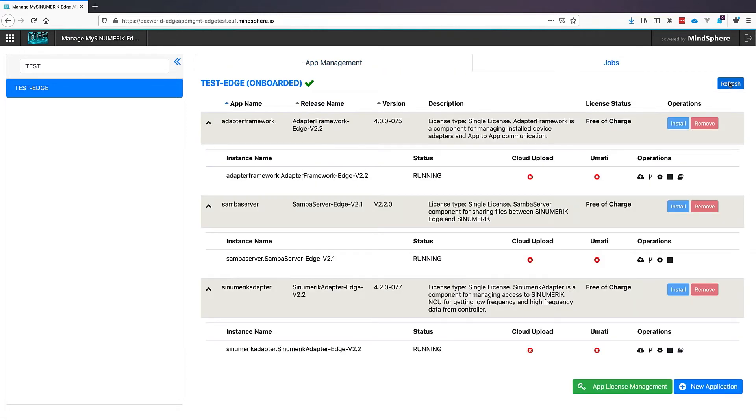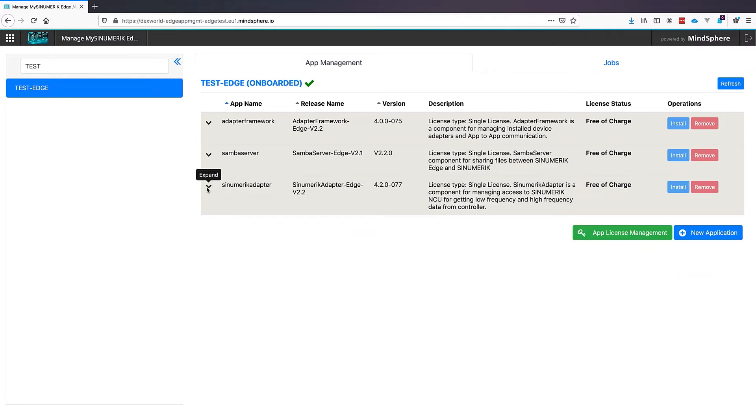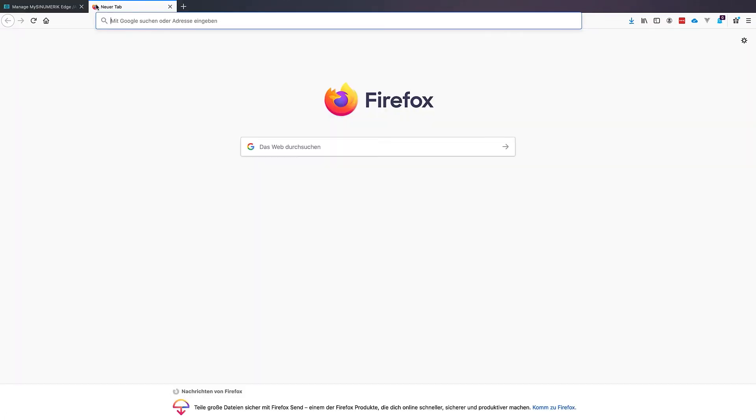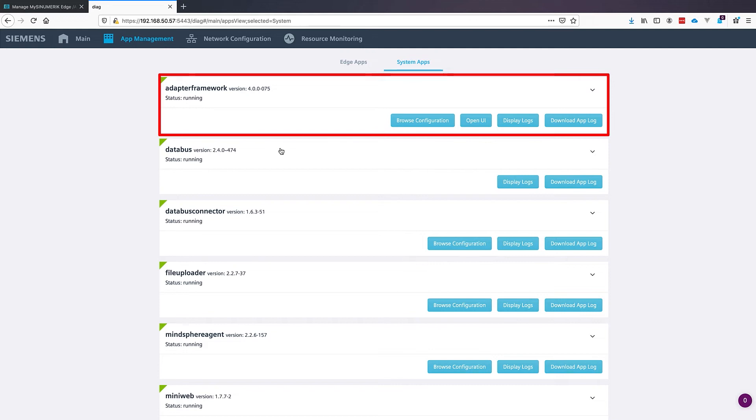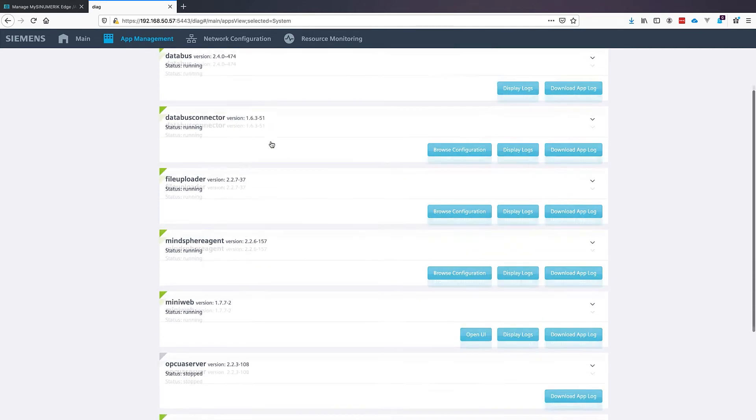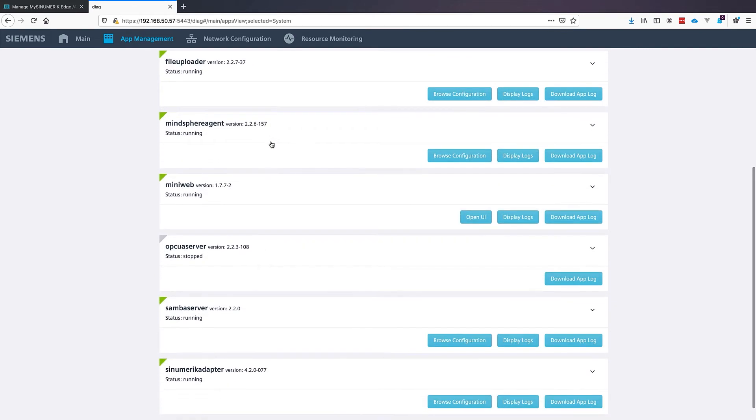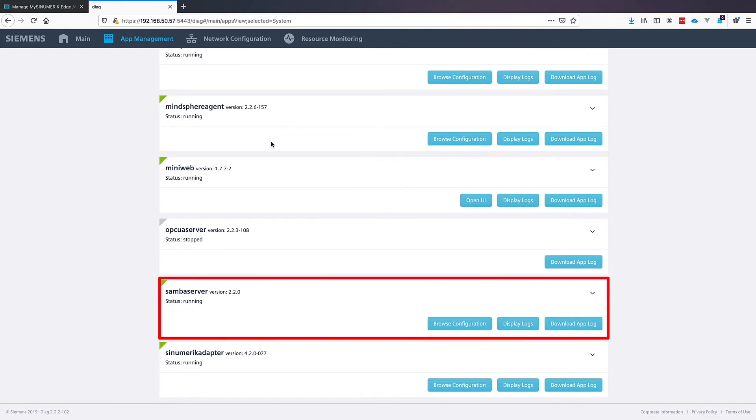To see if all applications are working well, we can first clean up our dashboard a little bit and open a new tab in our browser. And input the IP address of our Edge box, followed by the port 5443. This will open a diagnostic page from the SINUMERIK Edge box. And under App Management we are able to see the status of all applications running on our Edge box. In the left upper corner you see a green triangle that means that these applications are running. Same for our Samba server and SINUMERIK adapter.